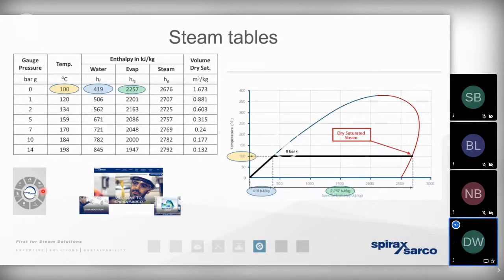But what we also need to remember is when steam gives up its heat energy, it condenses. So there's a change of state from a gas to a liquid. And as you can see, when steam gives up its heat energy and condenses, it's actually the enthalpy of evaporation. It's that latent heat. It's the energy that we added to the boiling water to make it change state. That's the energy that is used by the process. So in other words, that liquid condensate that is left behind, that retains the remaining sensible heat. So there's a lot of valuable information demonstrated here in the steam tables. It shows us the energy we need to put into the water to produce steam. It tells us how much energy we need to put into the water to bring it to boiling point.